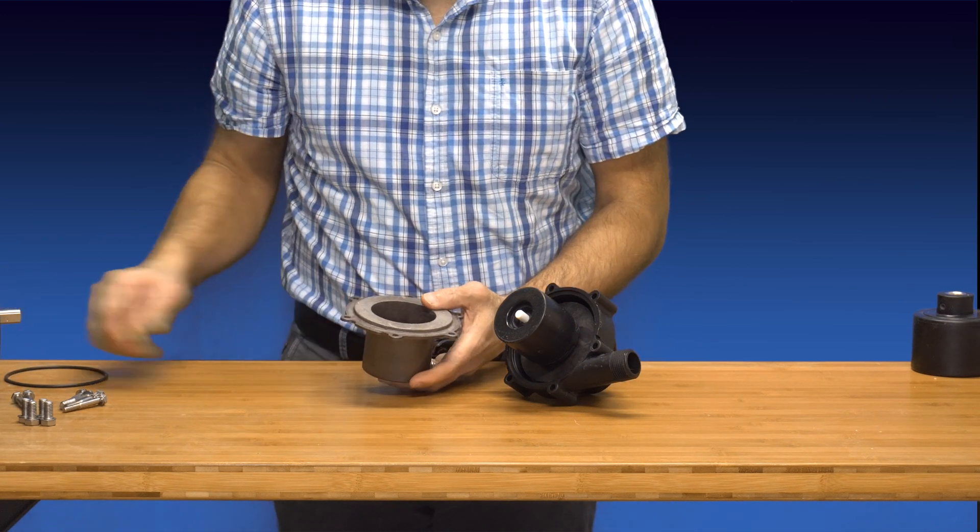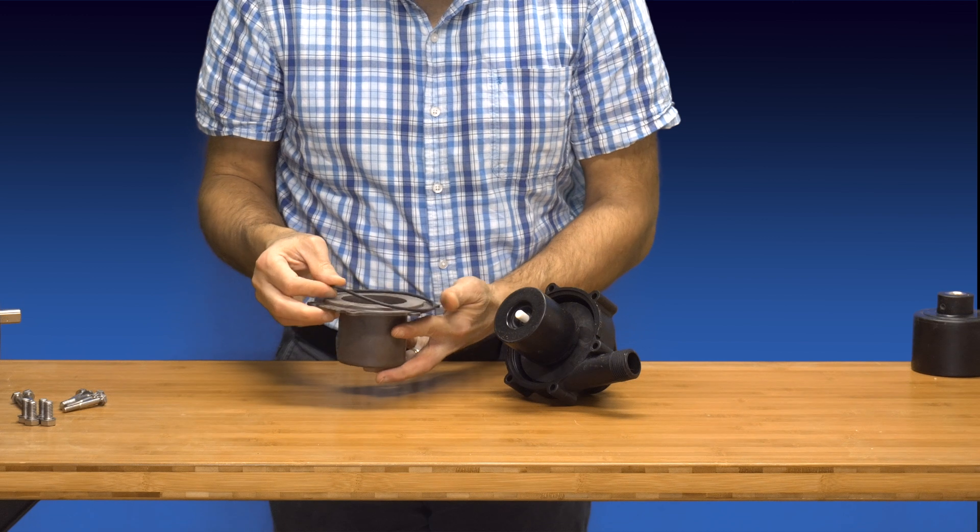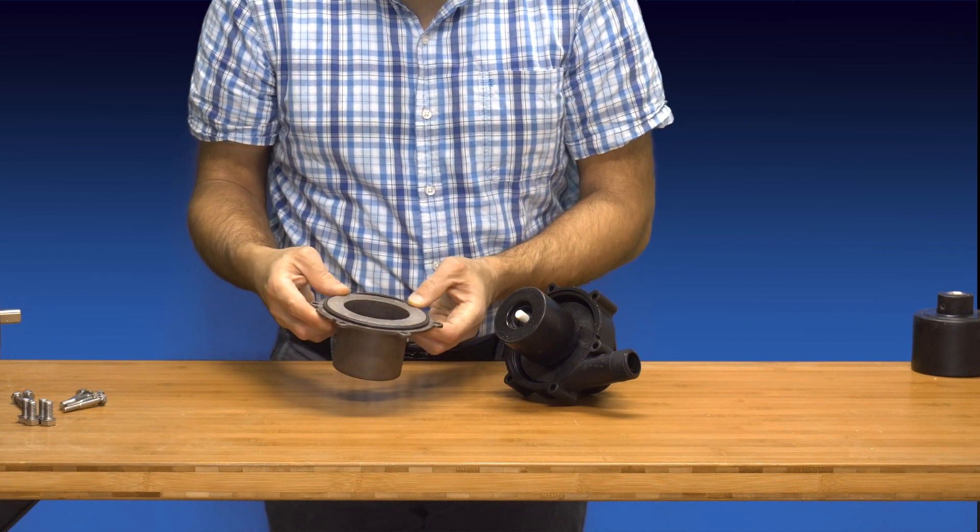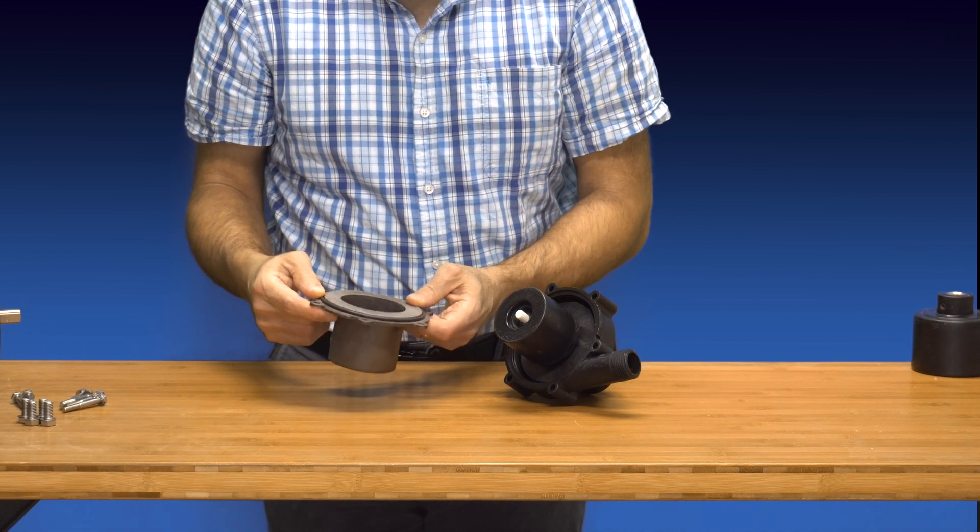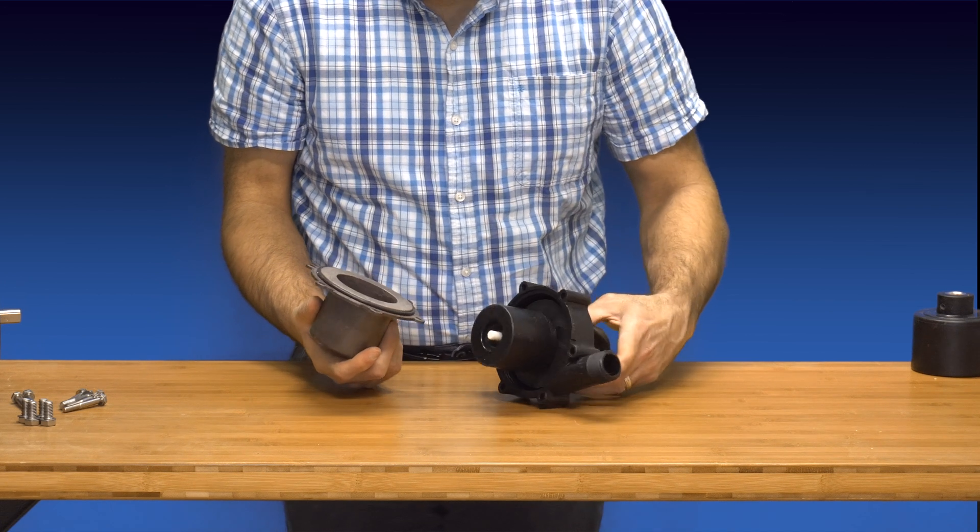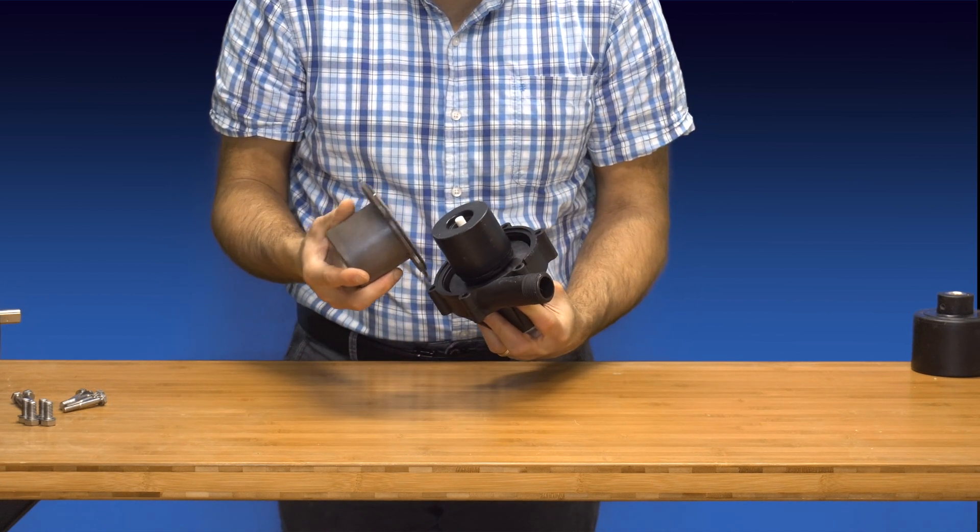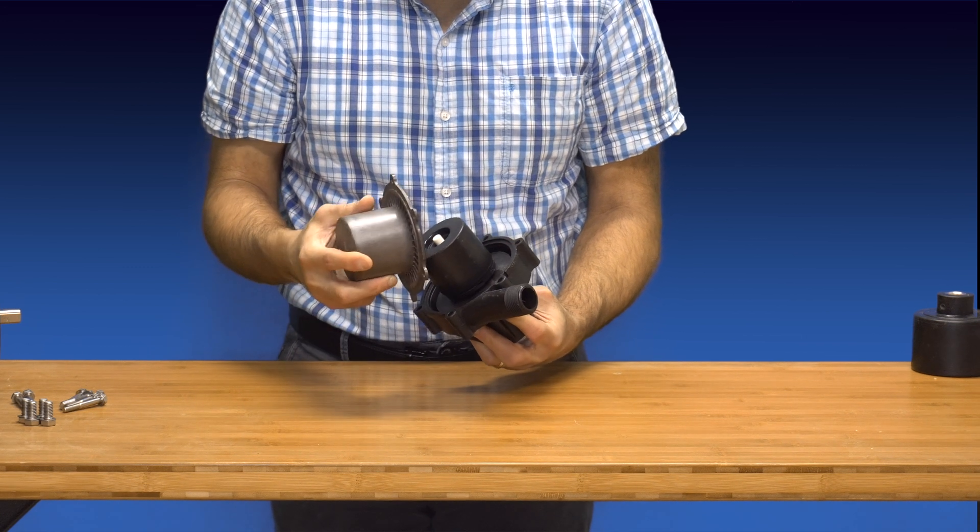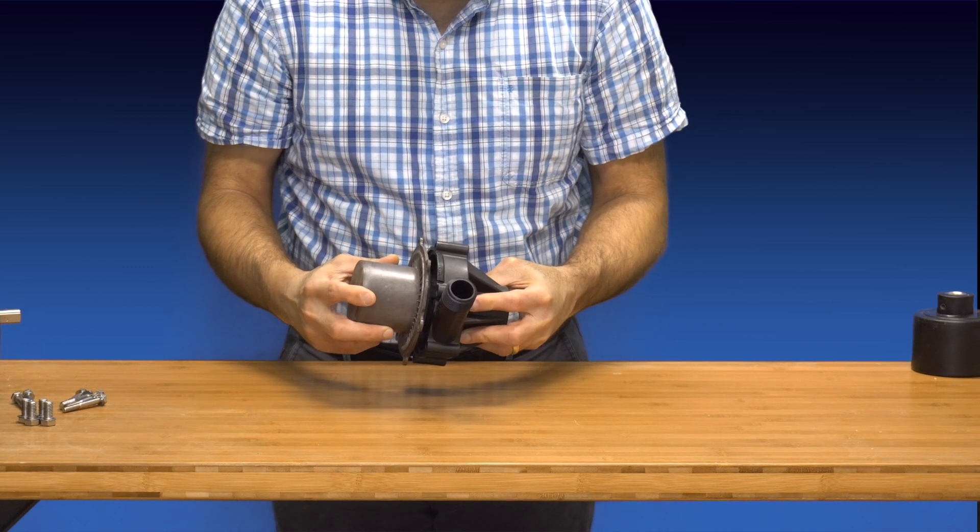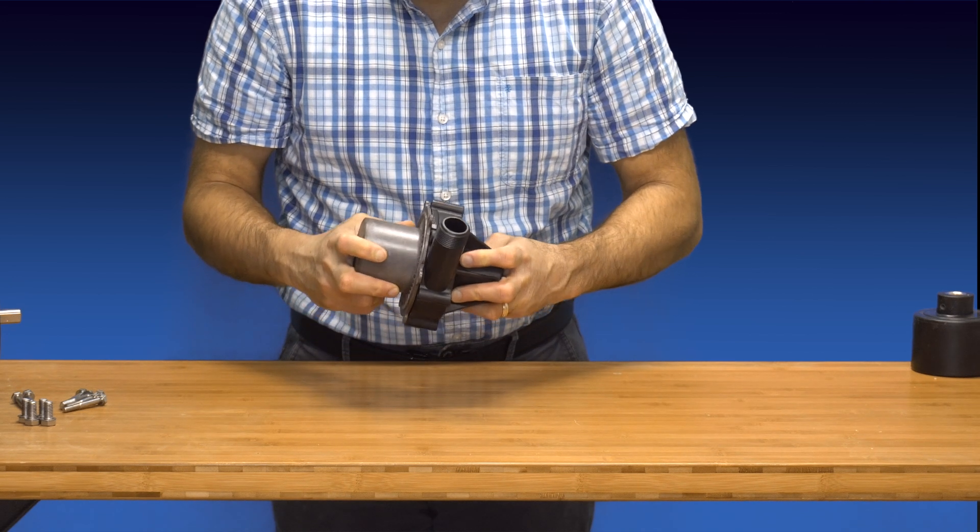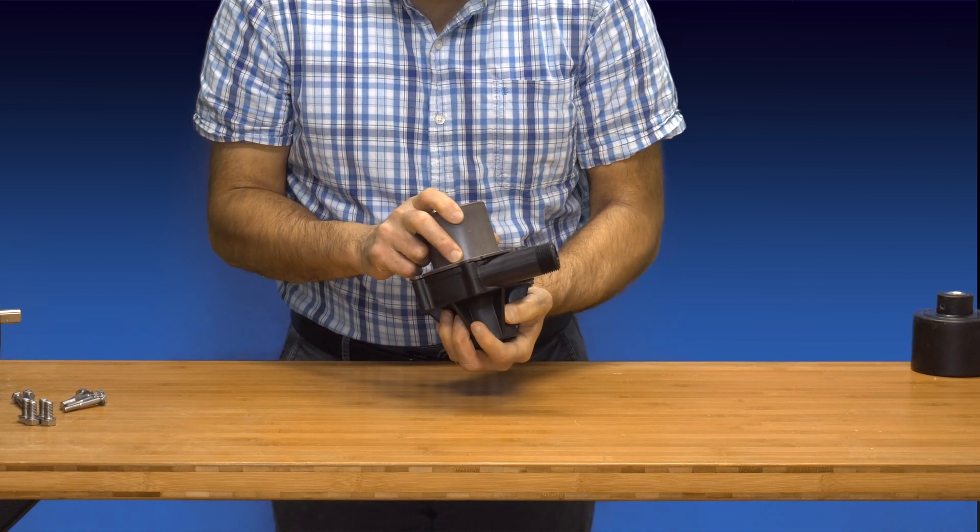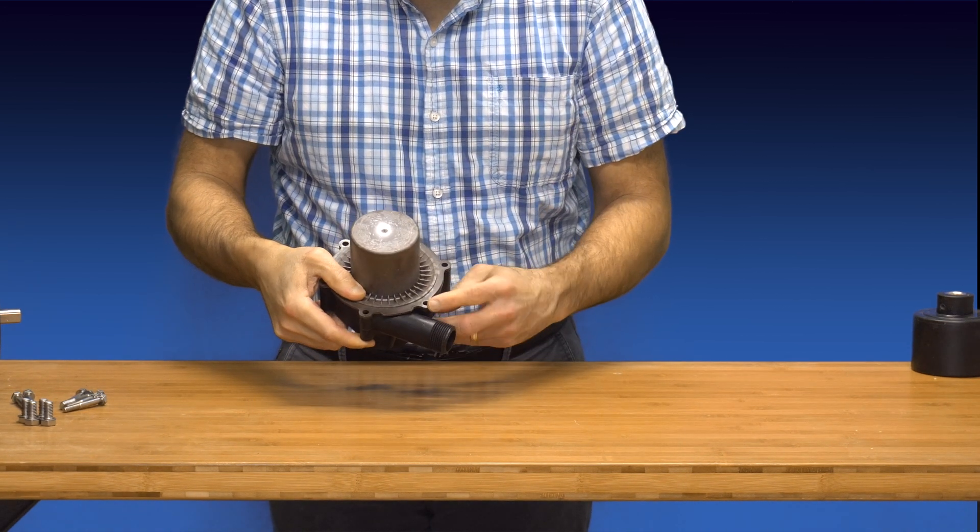Next, hold the rear housing in one hand and slip the O-ring over the front end of the rear housing. Now take the previously assembled front housing and impeller and combine it with the rear housing. Slip the rear housing over the back end of the impeller and engage the front end of the rear housing with the back end of the front housing. Also be sure to align the bolt holes on both parts. Seat the parts firmly together.